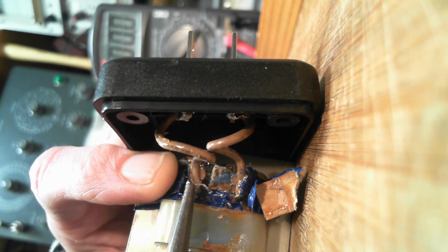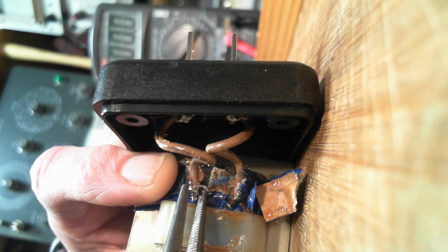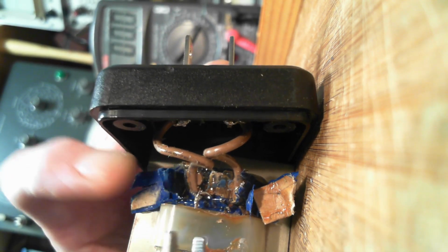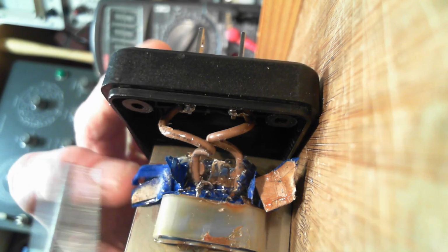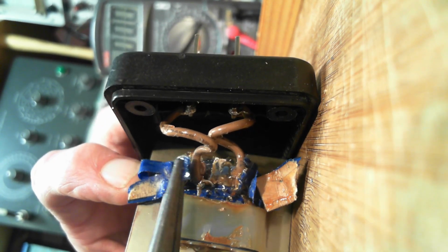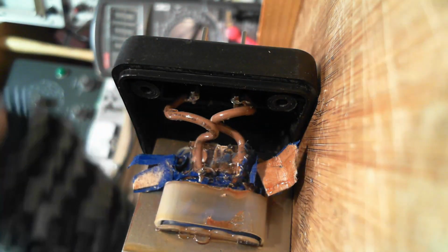If the overheating caused this to happen, but the fuses remain good, that suggests the heavy current was not going out of the transformer. That's a bit of a bad sign—it would further suggest a problem in the primary winding here.